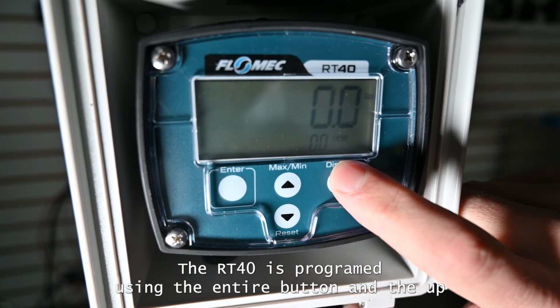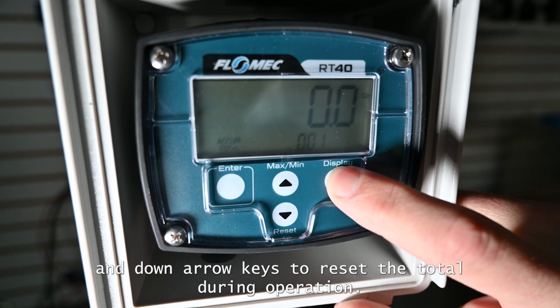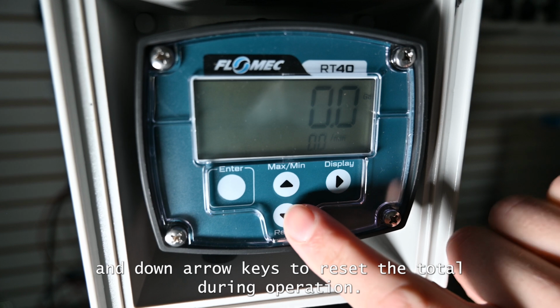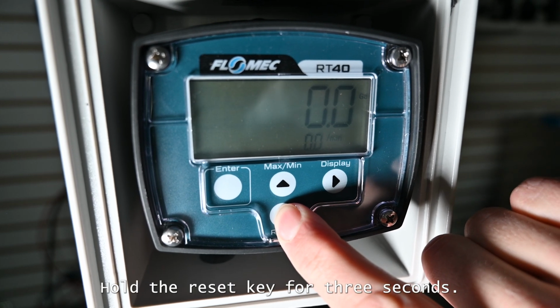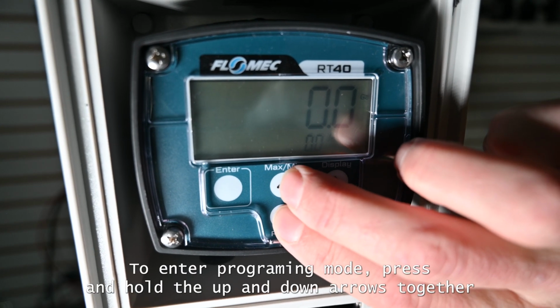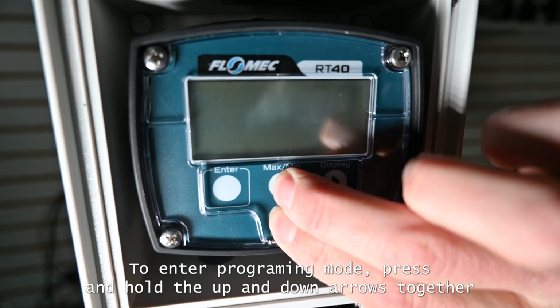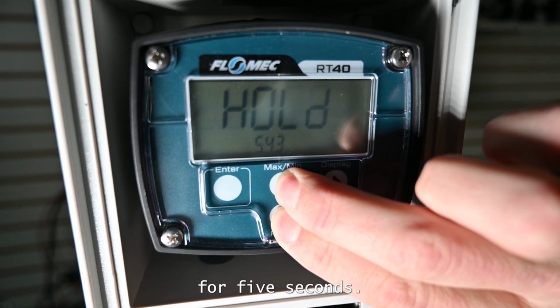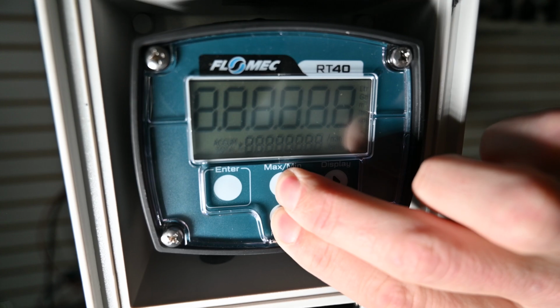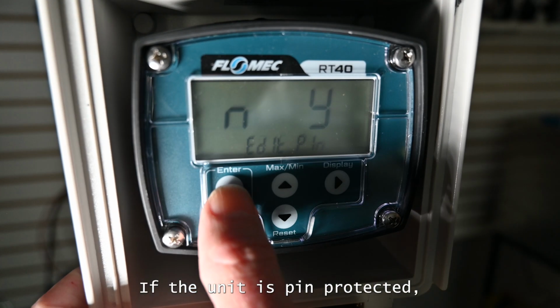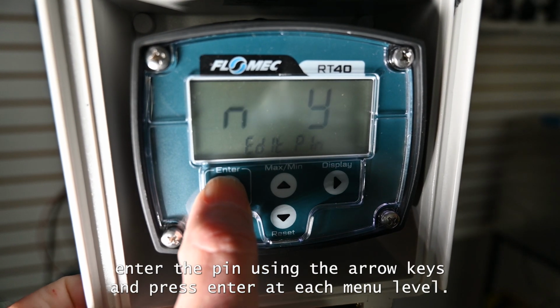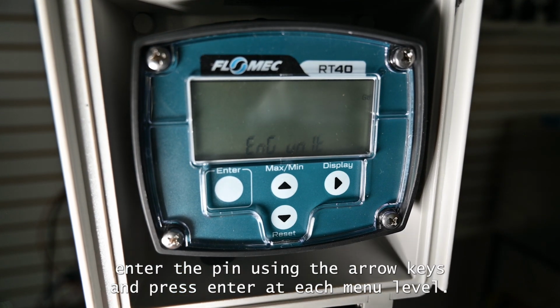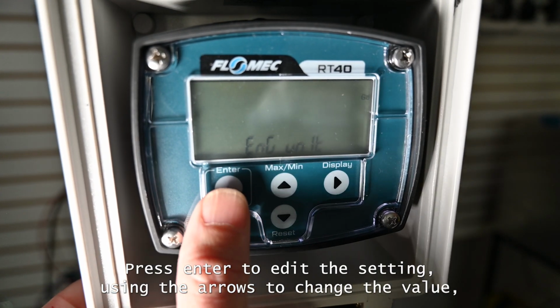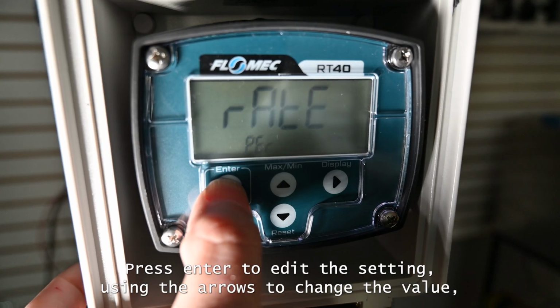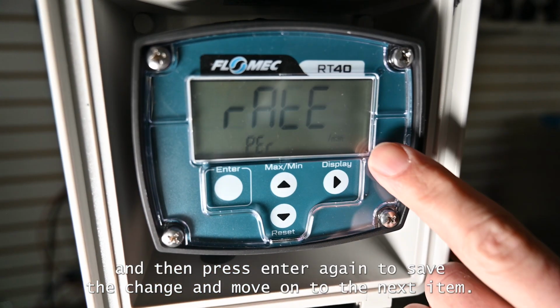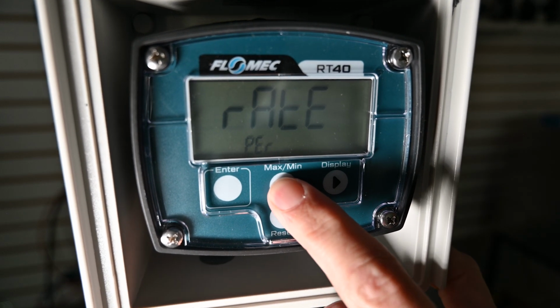The RT40 is programmed using the enter button and the up and down arrow keys. To reset the total during operation, hold the reset key for 3 seconds. To enter programming mode, press and hold the up and down arrows together for 5 seconds. If the unit is pin protected, enter the pin using the arrow keys and press enter. At each menu level, press enter to edit the setting, using the arrows to change the value, and then press enter again to save the change and move on to the next item.